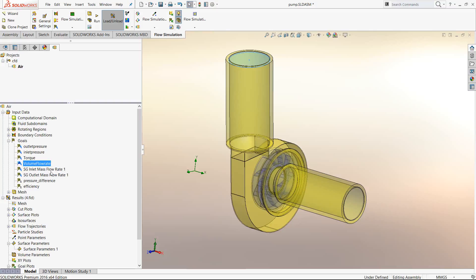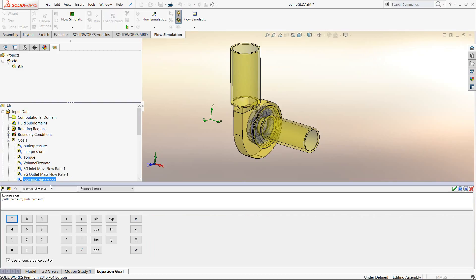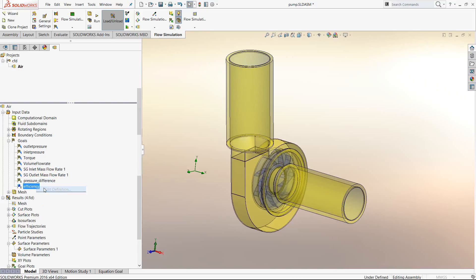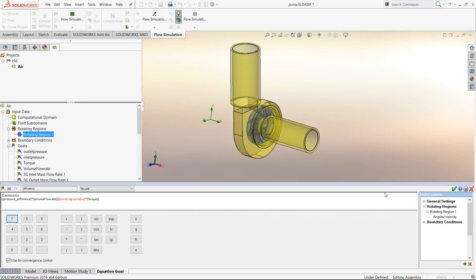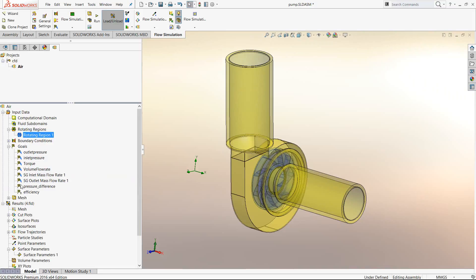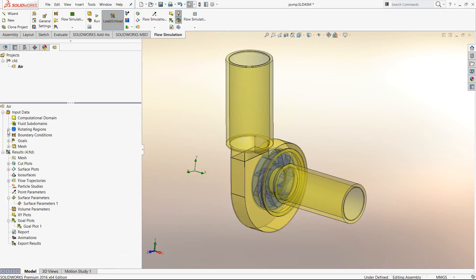We try to design the pump to optimize and increase values like mass flow rate and pressure difference. There is also an option to give an equation goal — for example, knowing the outlet and inlet pressures, we can calculate the pressure head created by the pump. Similarly, we can define an equation for efficiency. One variable in the efficiency equation is the rotational speed, which I select by double-clicking so it comes into the equation.